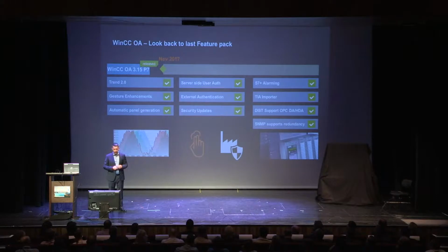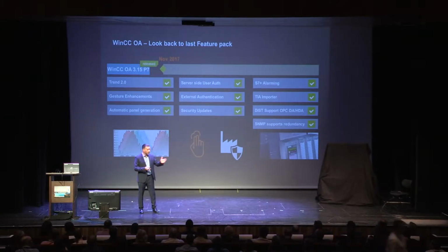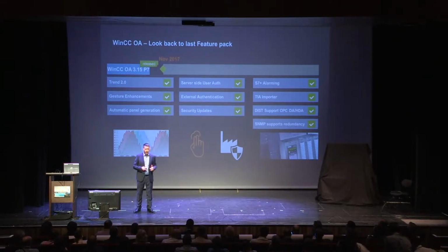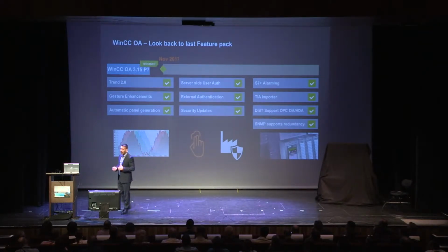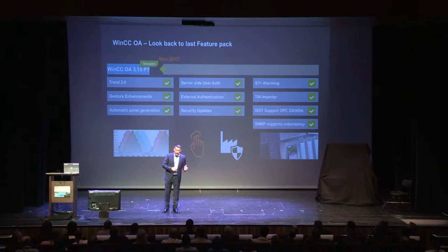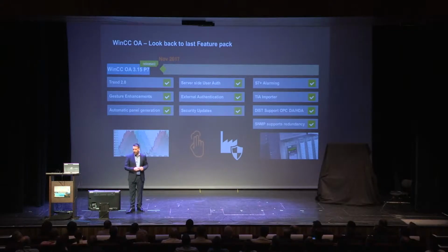Regarding TIA integration, we already had this demonstration from Martin Kumera. Thank you, Martin, for your tunnel demo. There he presented and demonstrated to you already the TIA importer. The TIA importer enables you to import engineering information coming from the TIA Portal directly into WinCC OA, which means that you don't have to insert all the information coming from the TIA engineering by hand. We also extended our S7 Plus driver in terms of alarming. Since feature pack 7, the alarms coming from the PLCs are now supported directly in WinCC OA.